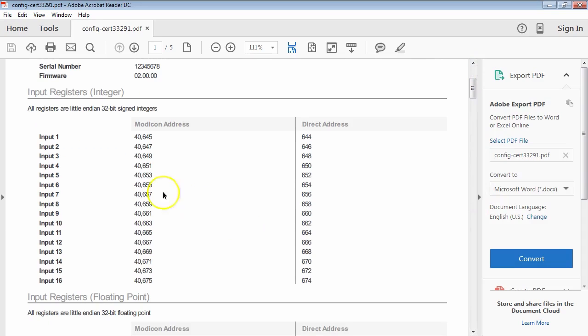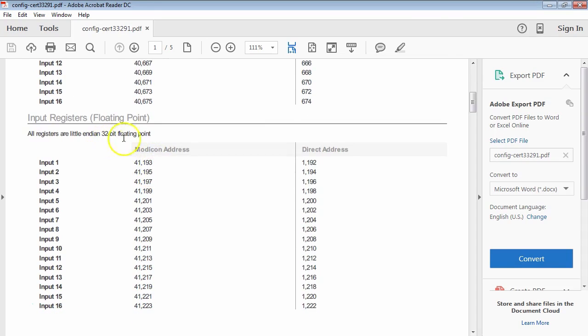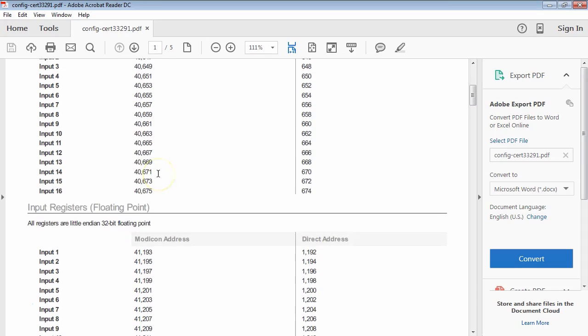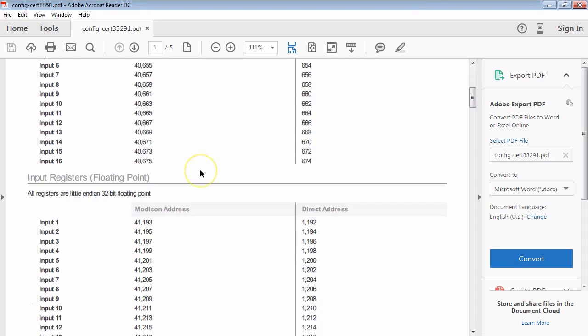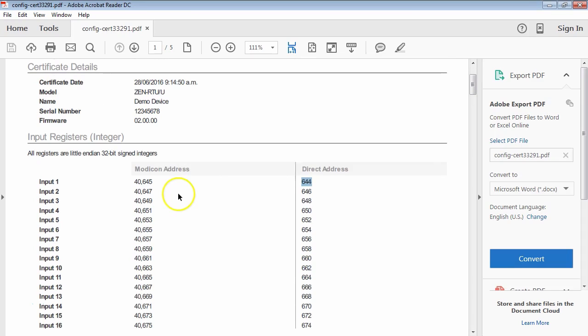You'll notice that for each input register we've got the Modicon address. This is the typical Modicon addressing format for holding registers, of 40,645. And then over in the second column we've got the direct address. This is the address that appears in the Modbus frame. If you're familiar with Modbus, this is the address that's decremented by 1 count from the Modicon addressing. You can choose whether you want to use 32-bit signed integers or 32-bit floating point for your values. All the values are little endian, and most PLC or SCADA packages will be able to cope with that.